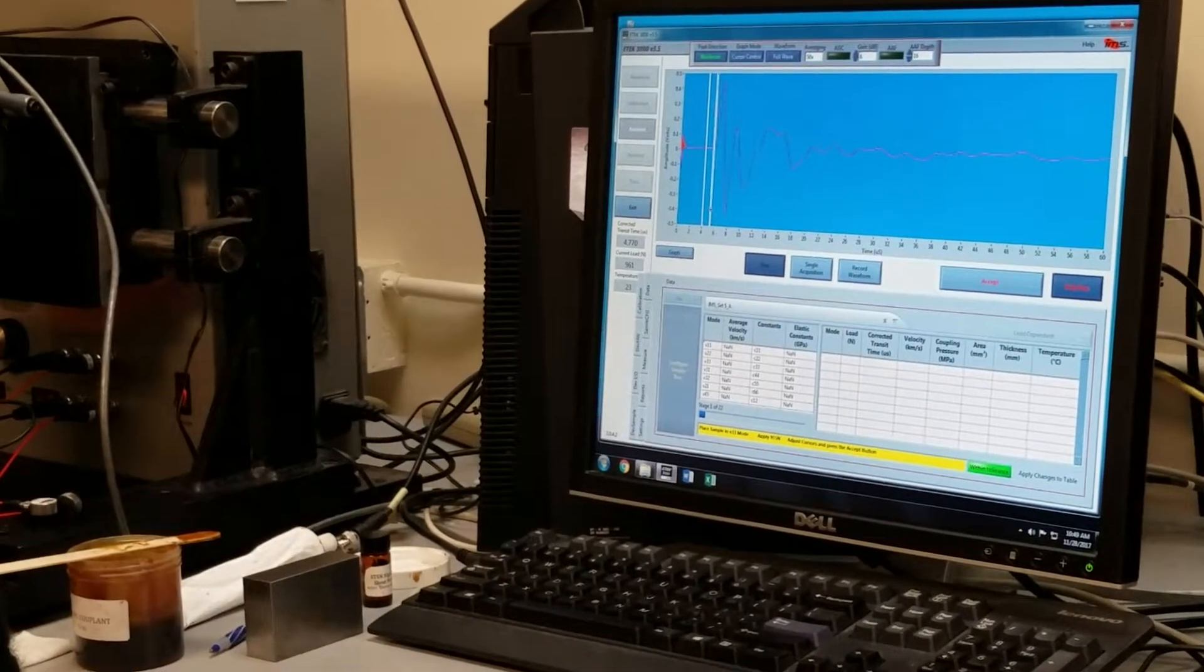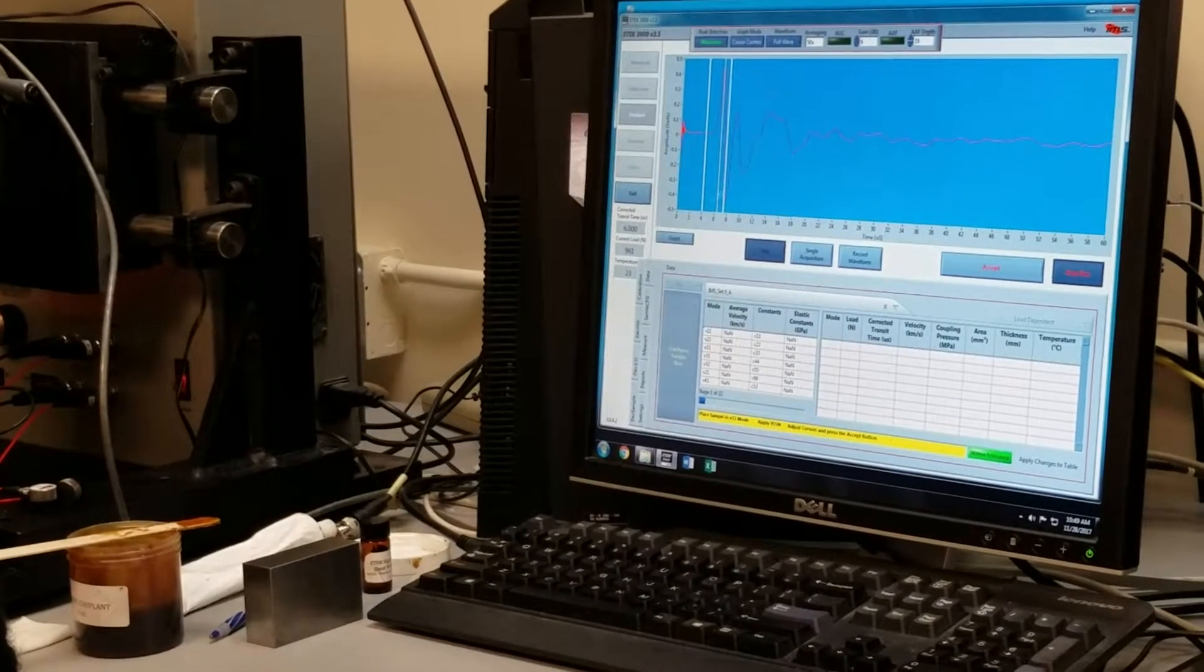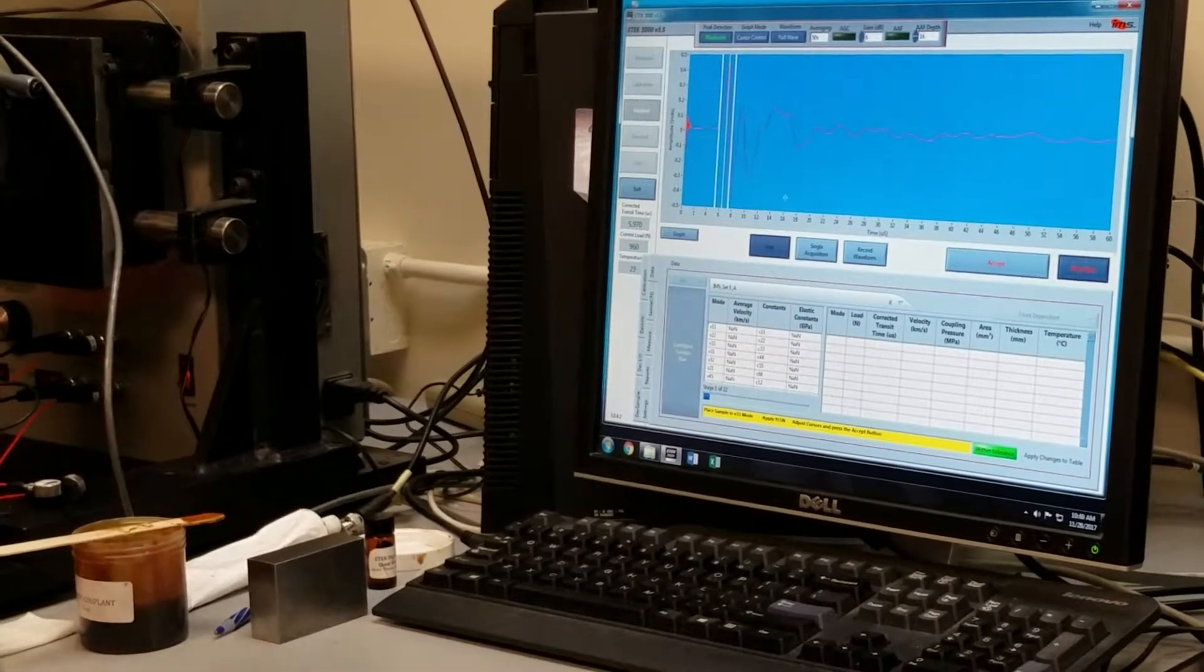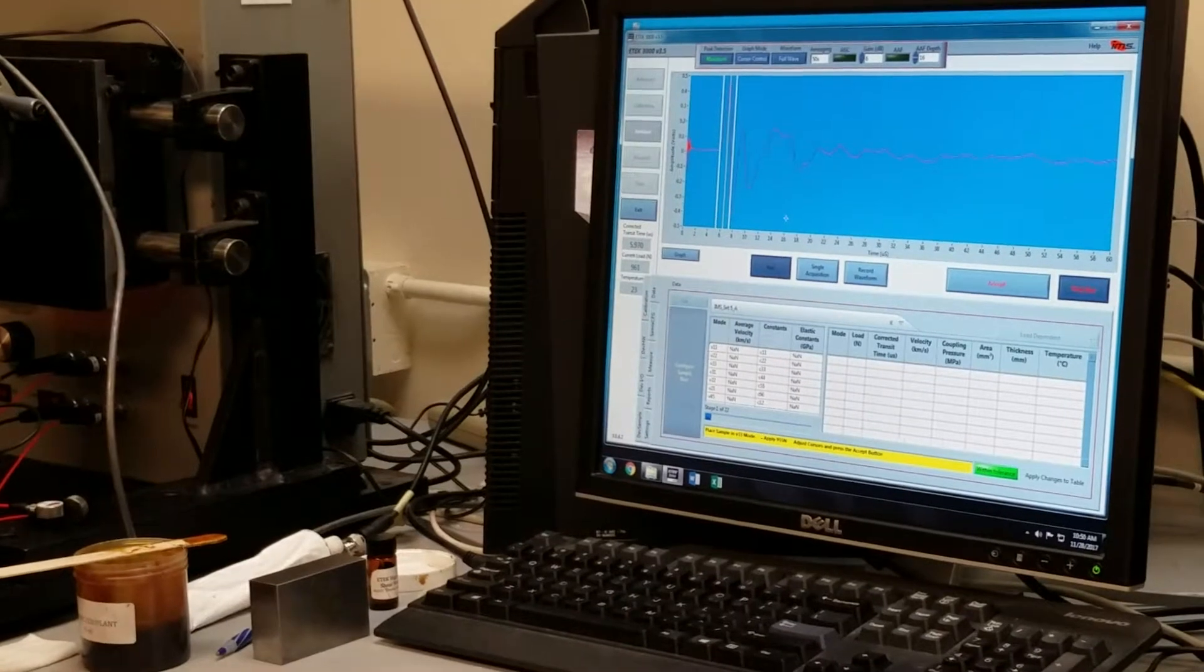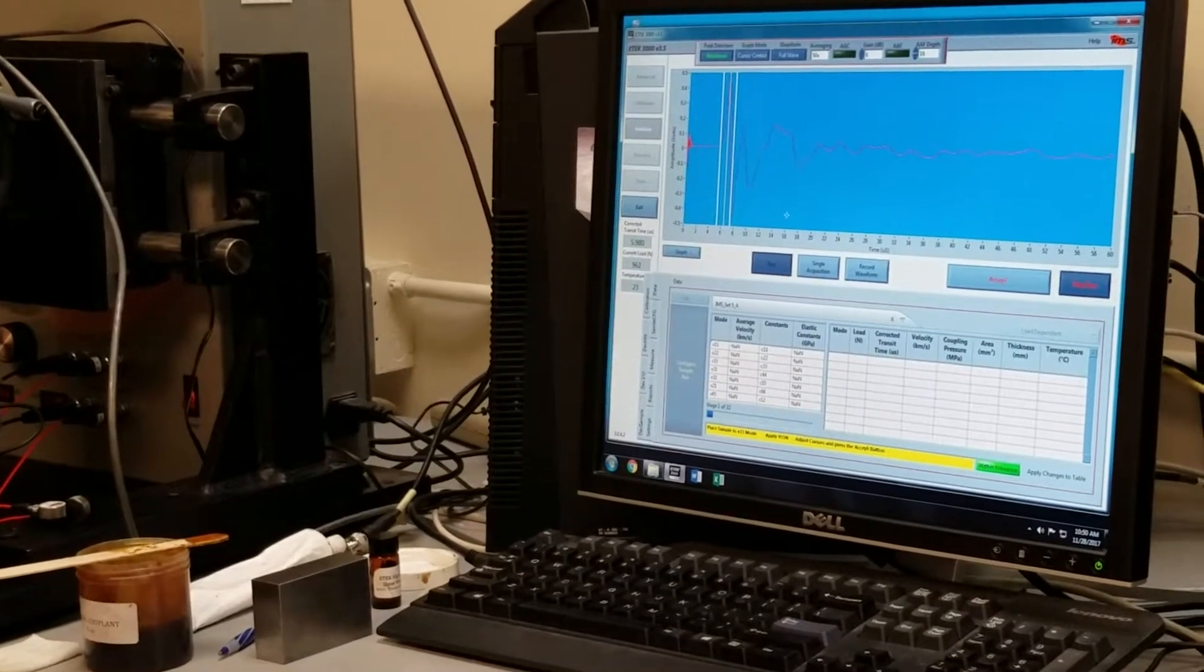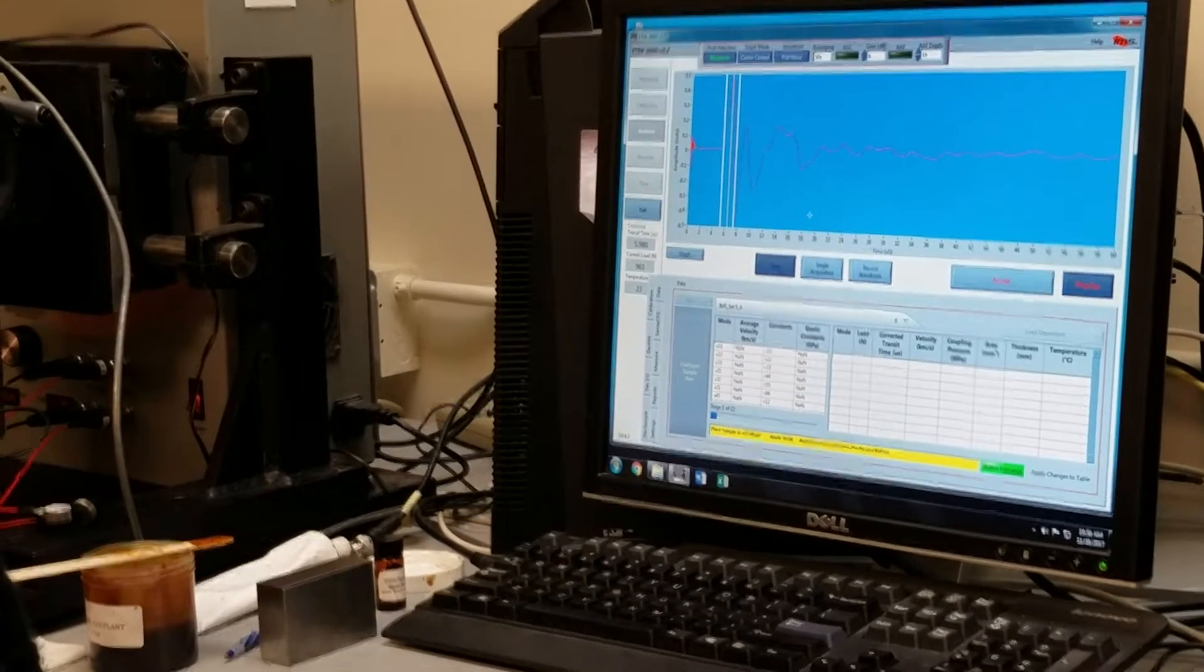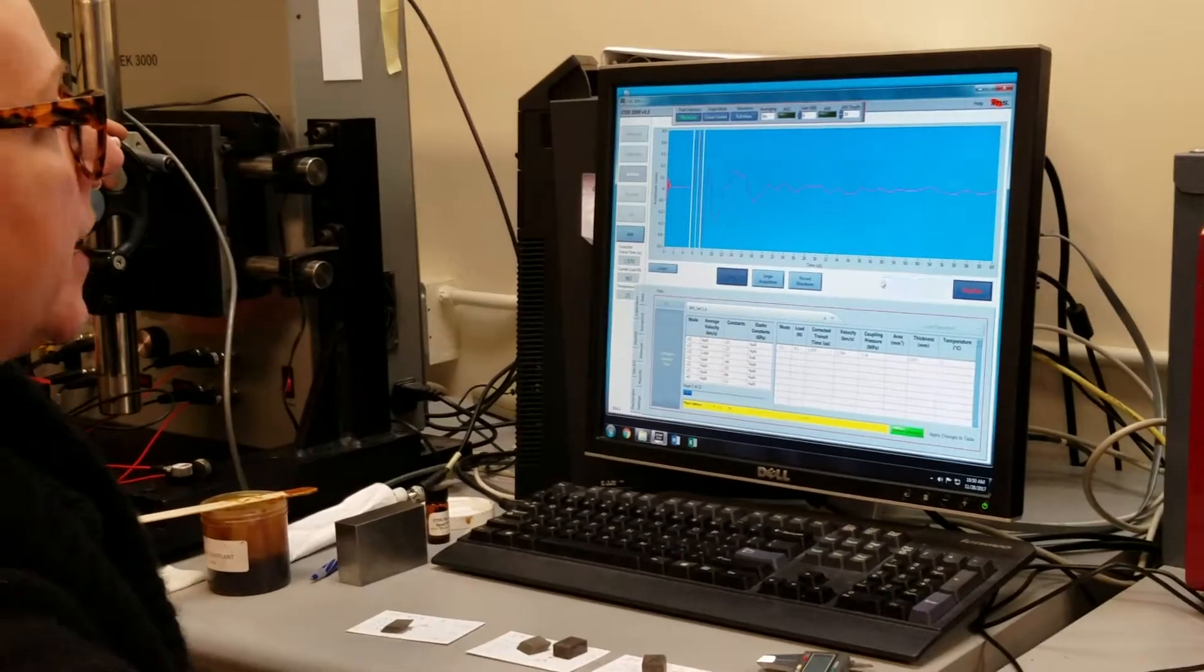I need to increase that to about 955, and now the peak of my waveform is off the screen. I've lowered the gain. I'm going to drag my cursor so that the yellow vertical line is measuring that first peak, and I'm all set to click accept.